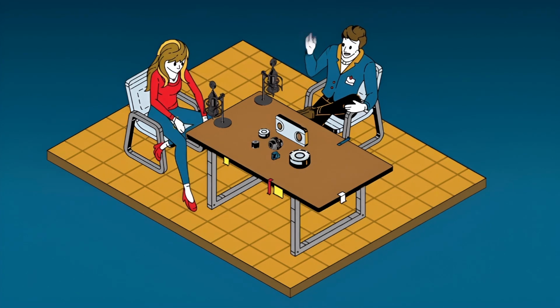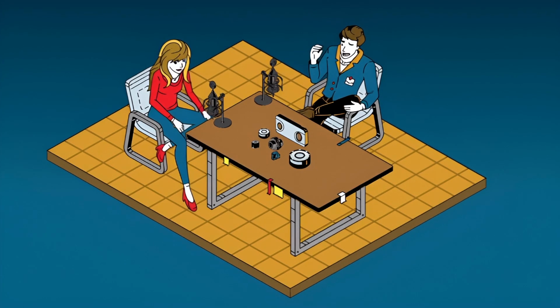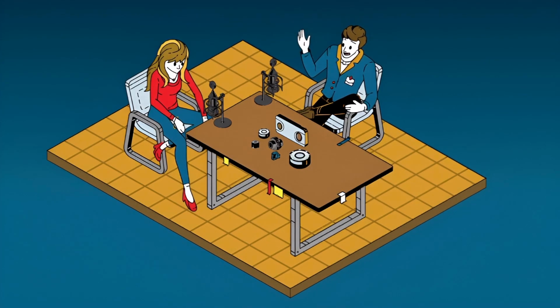And for those who need that defensible data, what does world-class calibration quality assurance actually look like? It's a rigorous process, and it's fundamentally tied to national standards. It involves using what are known as gold and platinum standard reference load cells. These are sensors that are maintained in the lab, and they're routinely certified by the highest metrological organizations, like NIST in the US. So those reference cells are the gold standard. They provide the known value you're comparing against. They do. They're ultra-precise measurement standards. The calibration process then couples these standards with metrology-grade test stands and proprietary software to deliver data that is NIST traceable. And that traceability is everything. It's the defensible proof that your sensor's accuracy is tied directly back to the international system of units.